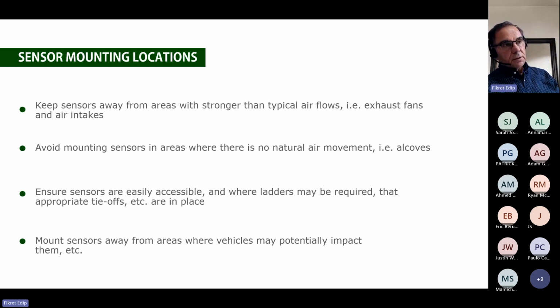So again, when designing a system, putting a gas detection system together, there are so many factors involved. We started from your target gas, then your application, what it is. You need to know how far apart those sensors need to be mounted, how high I'm going to be mounting them, and not only that, what type of sensor I'm using. If an engineer comes to me and says, I want a solid state sensor for a refrigerant application, I would say no, you're not going to get an accurate reading, because our main purpose from a gas detection system is to protect people and protect property.